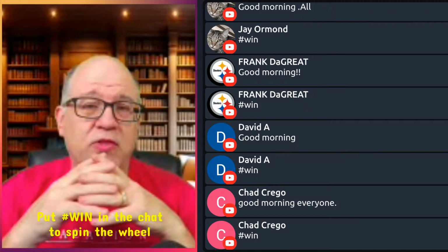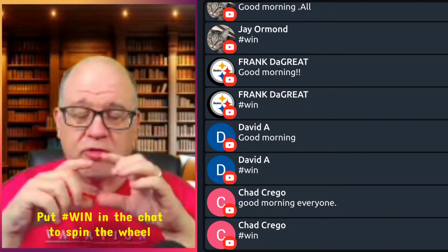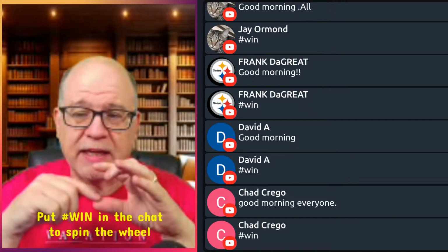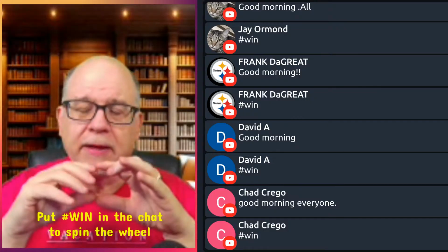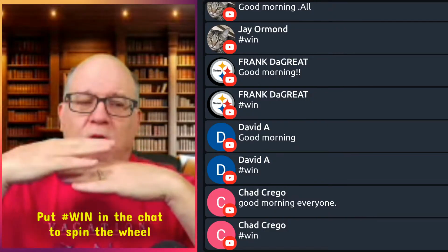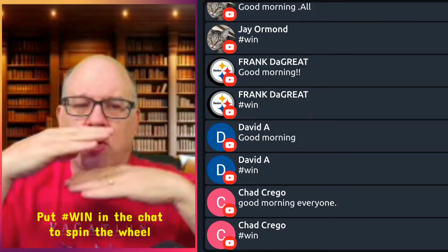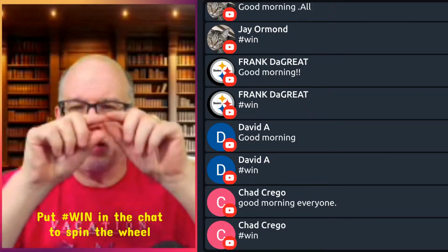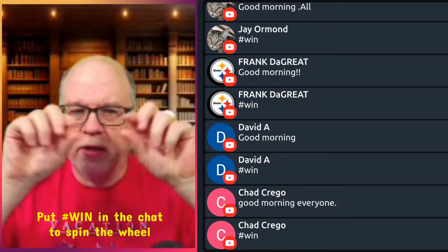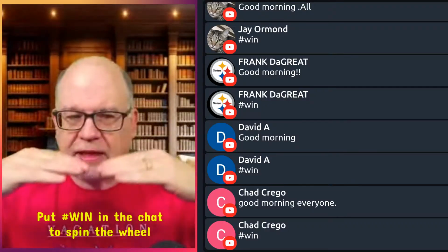And that means that you install them together as 2 single poles with an identified handle tie. And we'll look at the code here in a second. That if you put it so that those breakers are on top of each other, stacked. Remember the other day we talked about panel boards and how it alternates? So you've got 1 and 2 and 3 and 4, how it alternates down the bus.